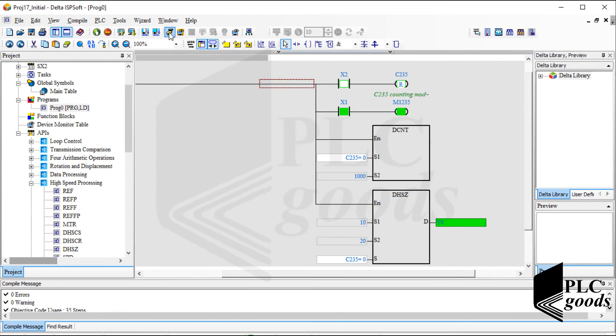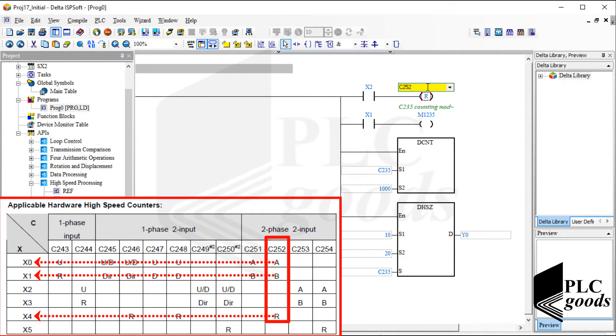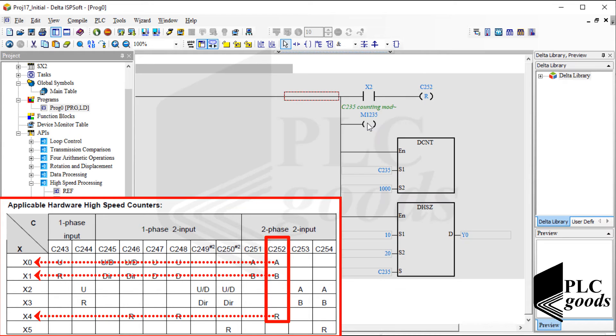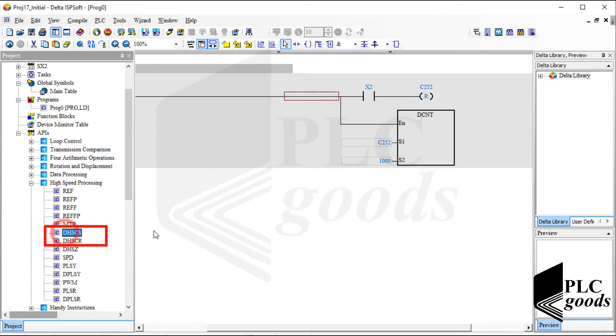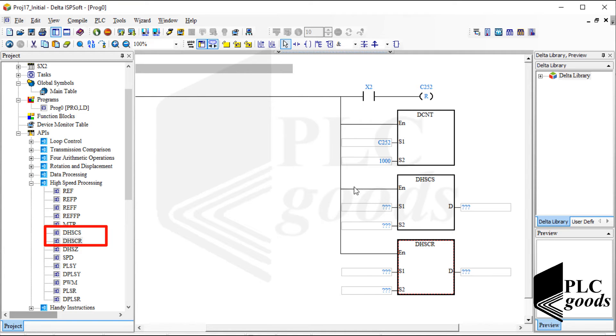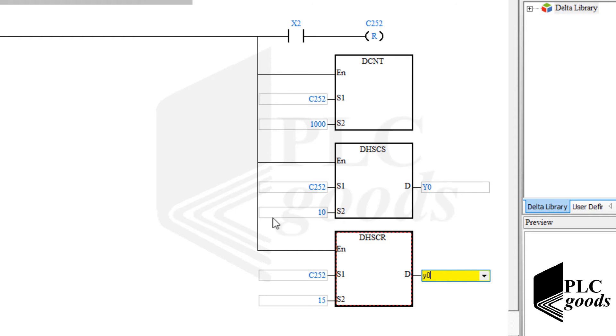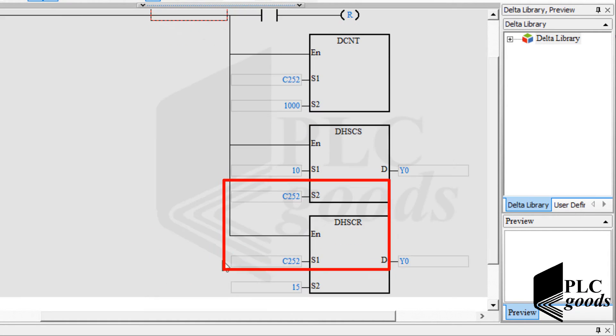Now let me exit from the online mode and use a hardware high-speed counter, C252, that uses three digital inputs. Instead of the DHSZ instruction, let me use two instructions — DHSCS and DHSCR — which set and reset a bit address immediately when the related high-speed counter reaches a certain value. There are two errors inside my program: I should enter the desired values and then determine the counter number for these instructions.